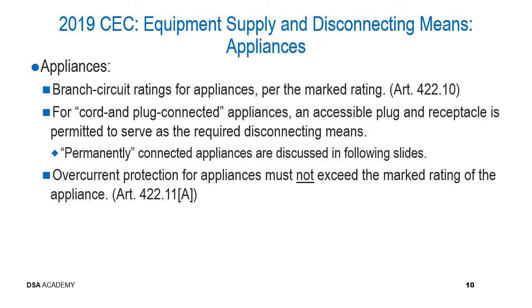Now we're going to talk about the disconnecting means associated with appliances. Now for appliances, the branch circuit ratings for the appliances must be per the marked rating, which is verified in Article 422.10. We've got some interesting exceptions permitted for cord and plug connected appliances, in that an accessible plug and receptacle is permitted to serve as the required disconnecting means. Now this completely makes sense from this perspective. If we understand that the purpose of the disconnecting means is personnel safety when working on energized equipment, then if the maintenance personnel can easily disconnect the power from these appliances by unplugging the cord, then that is certainly sufficient.